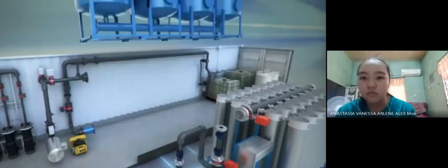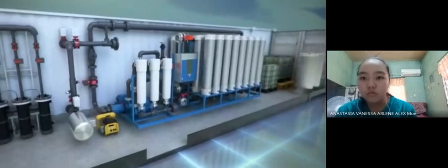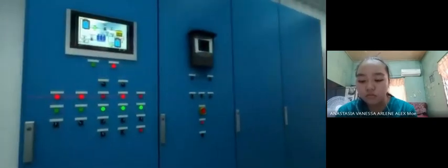The media filter is periodically backwashed to the source to reduce operator maintenance. If enhanced filtration is required, ultrafiltration technology can be utilized in place of media filtration to provide a 10x improvement in filtration. Before leaving the system, the water passes through an auto-actuated valve that analyzes real-time water quality in order to ensure that the effluent water meets all operator programmable targets. Finally, this entire treatment process is controlled by a process automation system complete with a touchscreen controller. This system minimizes labor and keeps operators aware of critical process diagnostics by sending out phone or email alerts during system operations.